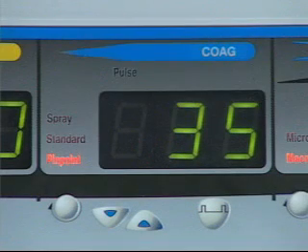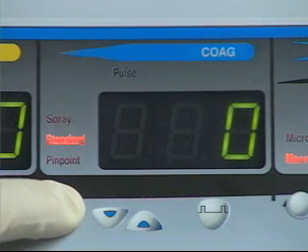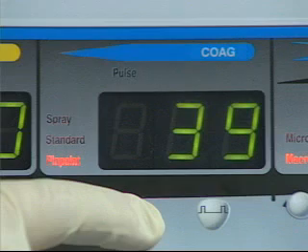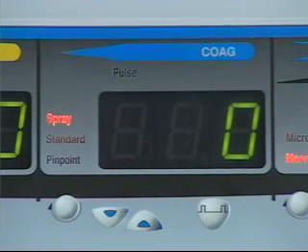Next, select the appropriate Coag function and power level in the same manner as was done with Cut. Simply scroll through Spray, Standard, and Pinpoint, and adjust the power by depressing the Up and Down keys. Spray Coag provides the widest pattern hemostasis with minimal thermal penetration. The non-contact delivery of Spray Coag makes it optimal for cardiovascular, liver, spleen, and trauma applications.